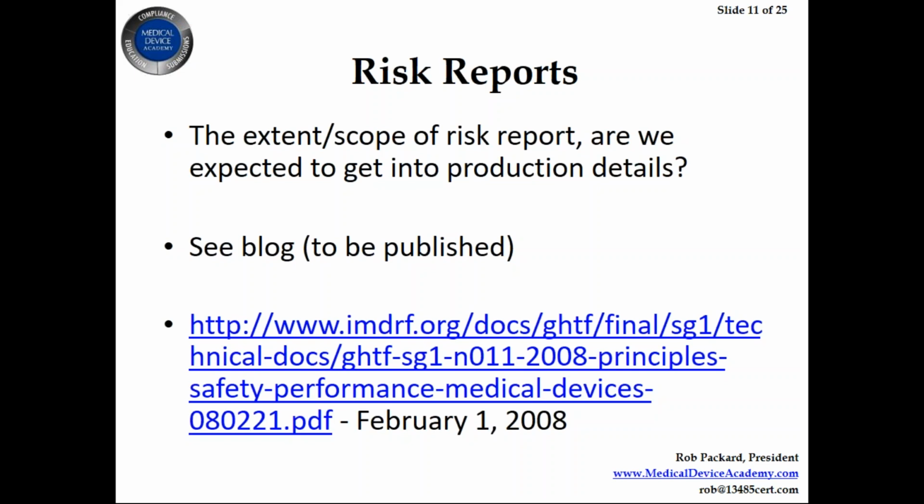But the FDA does recognize ISO 14971 for risk management, and when the inspectors come on site 2 years after you have received your 510K, they will look to see that the risks that you have identified in your risk management file match up with the complaints that you're seeing and the adverse events you're seeing, and they expect those to be updated when necessary. And if you're not doing that, they're going to indicate that you get a 483 because you haven't identified these risks that are in your complaints and your adverse events in your risk management file. So that's something they'll specifically be looking for during the inspections that are routine rather than during the 510K clearance process.